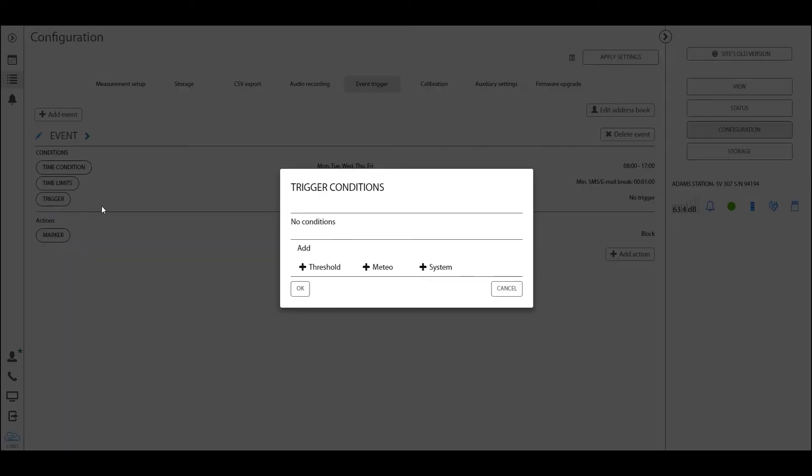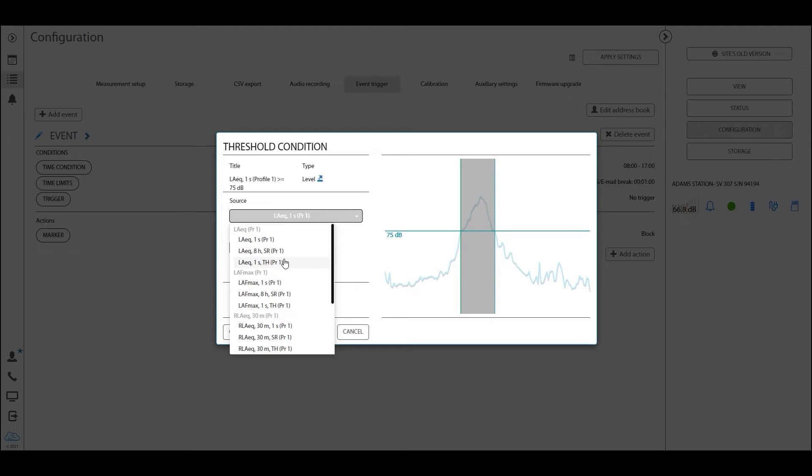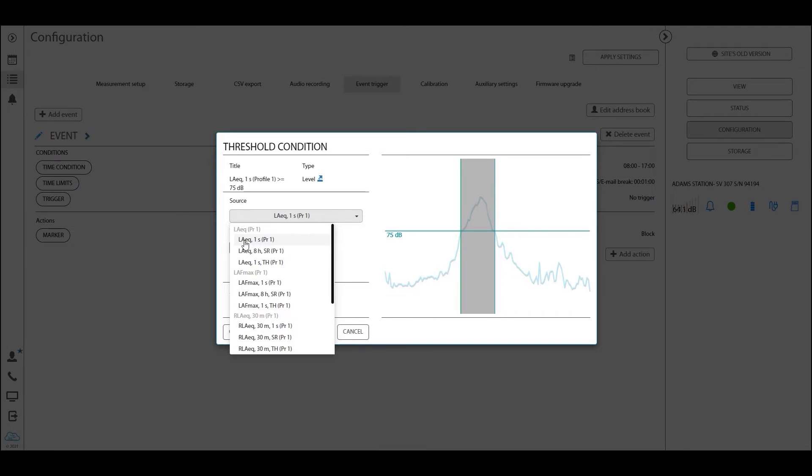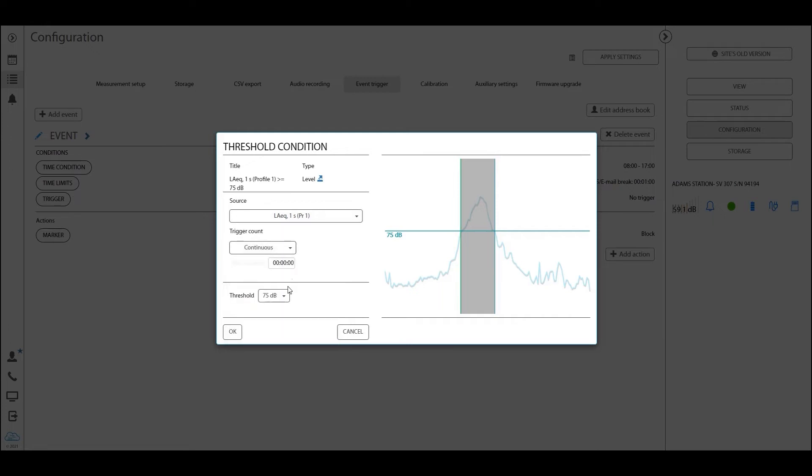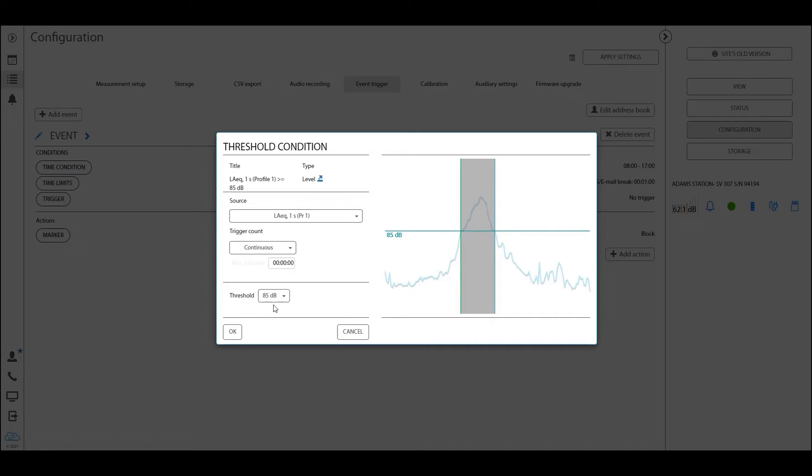Now we must define a trigger for the 307. A trigger can mean three different things. The most common one is a trigger of a threshold. If we click here, we are able to define what kind of noise and data should be triggering this level. Now per default, it's always going to be choosing from the source of profile one. Remember how we said that the measurement setup dictates all the other panels. Now in this scenario, we have set the A weighting to be set for profile one. Thus we can define an alarm on the equivalent level A weighted with one-second integration period. We set the threshold here for that noise. Let's say we want to be alarmed every time the threshold passes 85 dB, and the source of the noise is the LAeq. The trigger count is continuous, meaning that for this alarm to be triggered, this only has to happen one time, and there is no minimum duration.